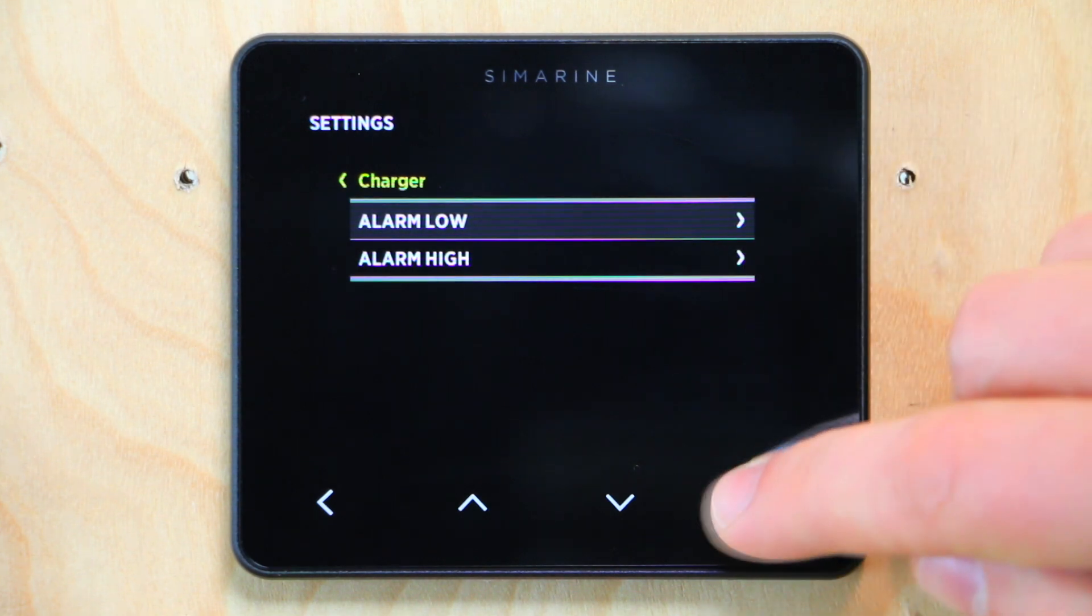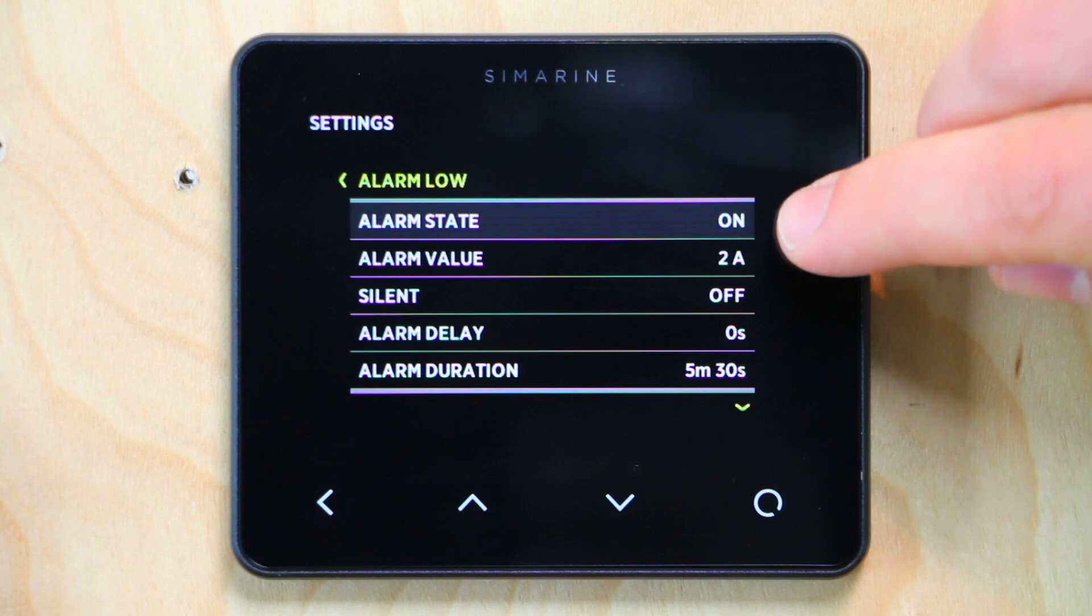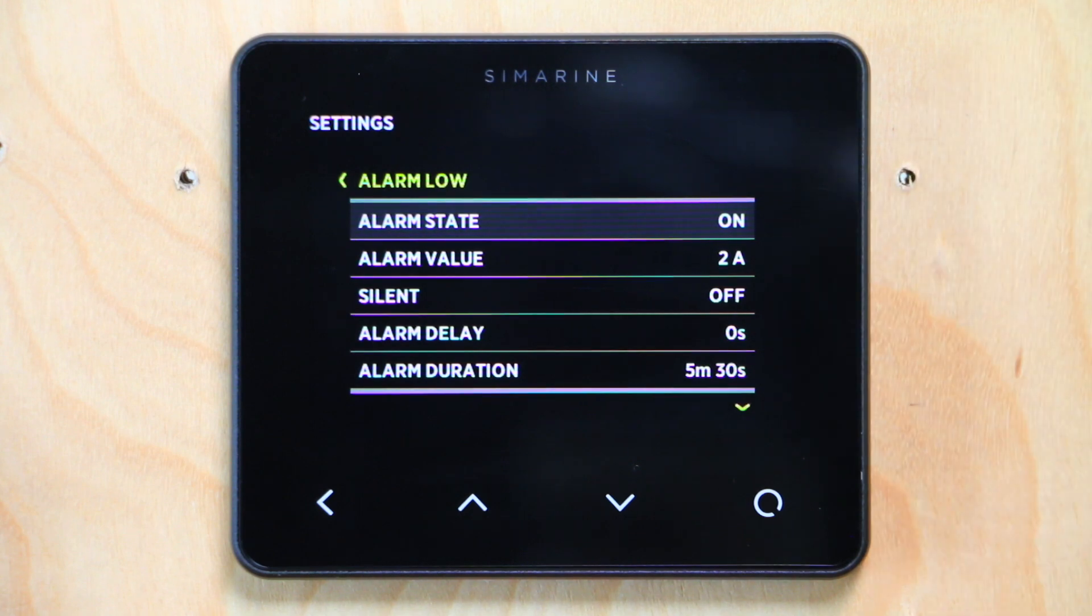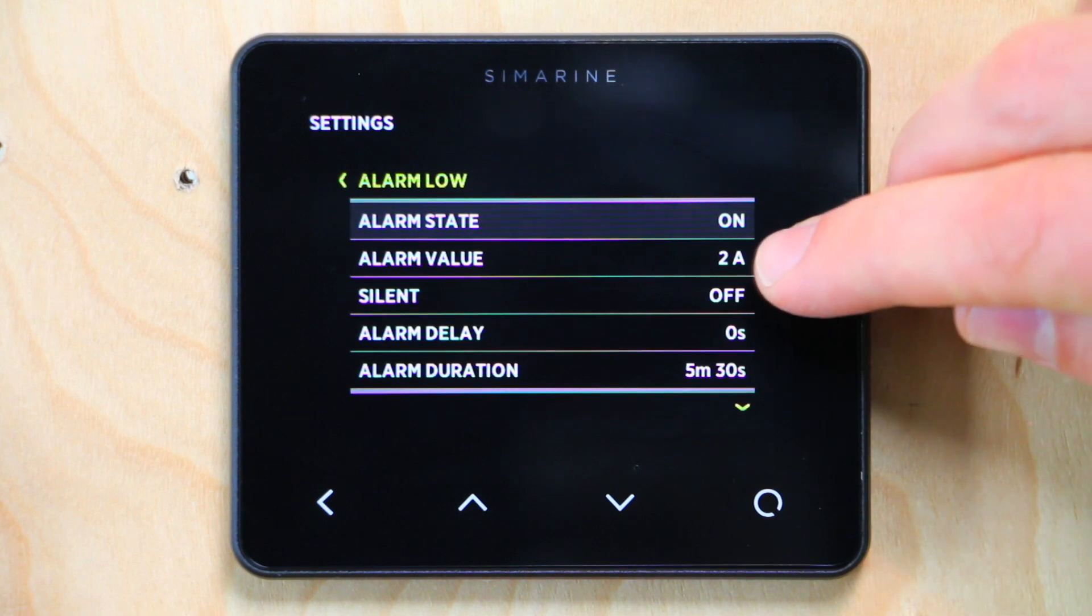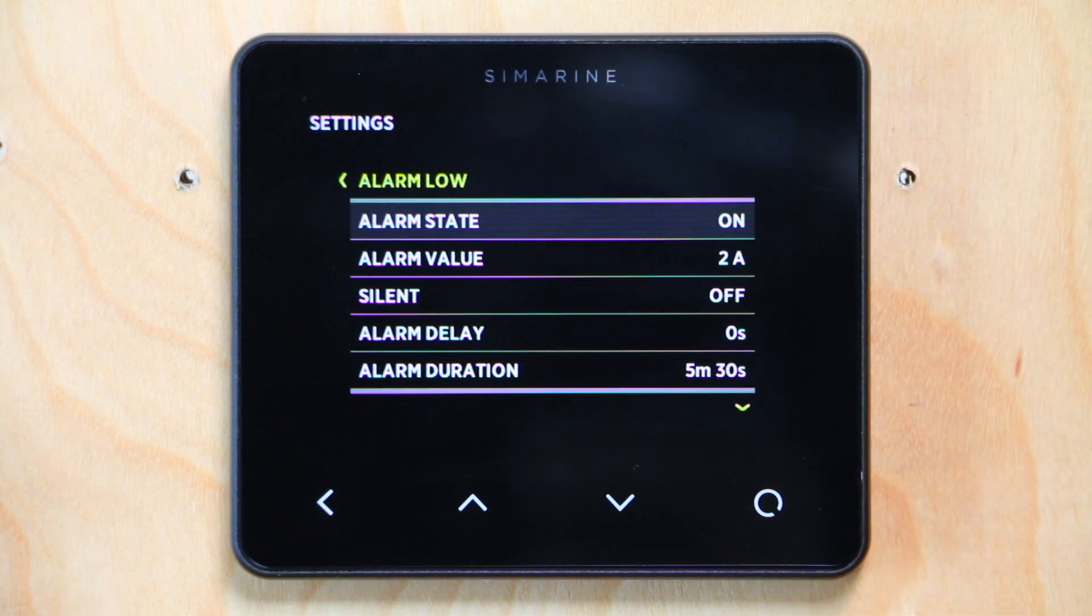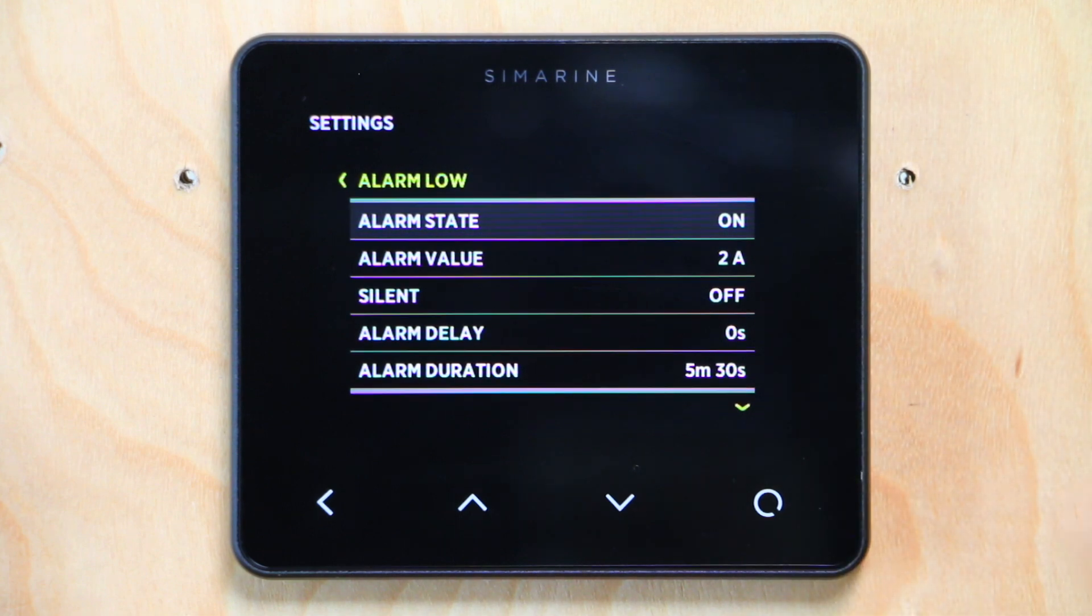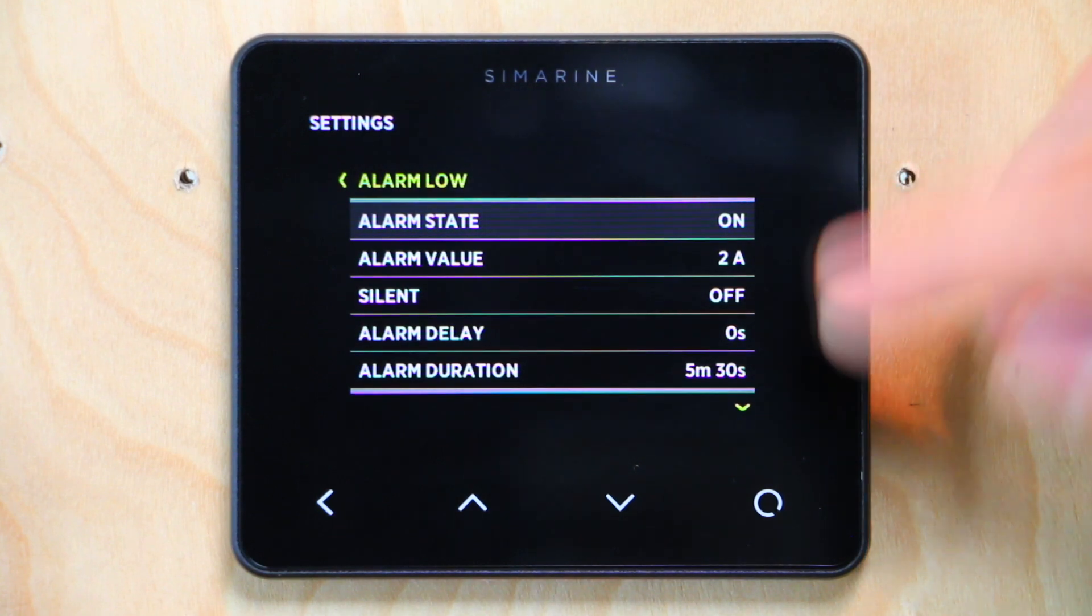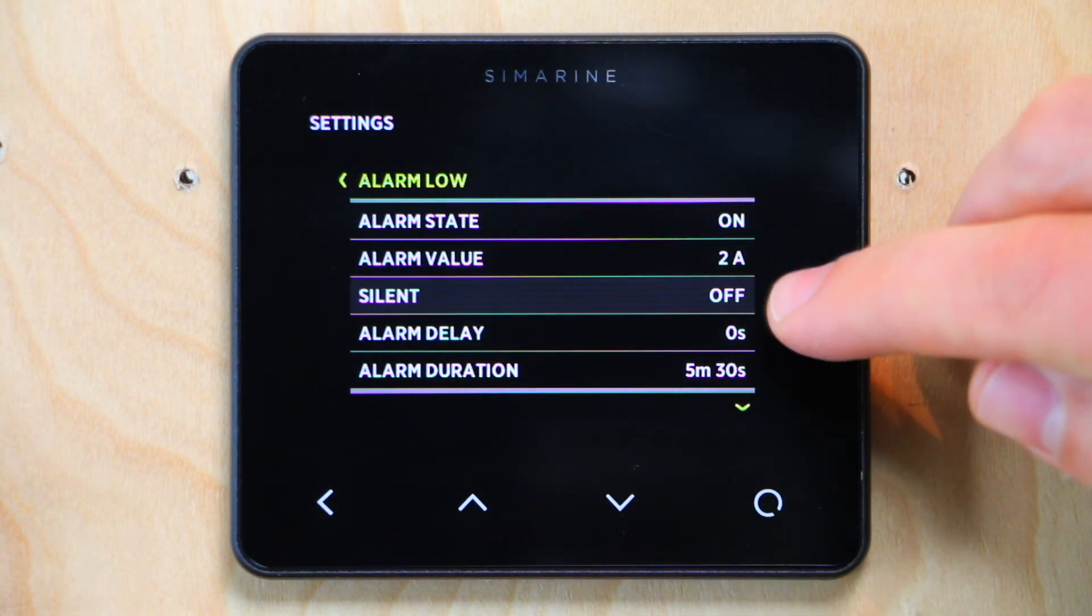Let's go into charger and alarm low is the alarm that I've set up. You can see alarm state is on. By default, this will say off. You just need to turn it on to say yes, I want to use this alarm. Alarm value, I set that at two amps. That's the threshold at which if it goes below that, the alarm goes off. If this was an alarm high programming, that would be the value at which if it went above two amps, it would go off. Whether you're on low or high, you're going to set a value, and if it goes below or above that value, it's going to go off into an alarm.